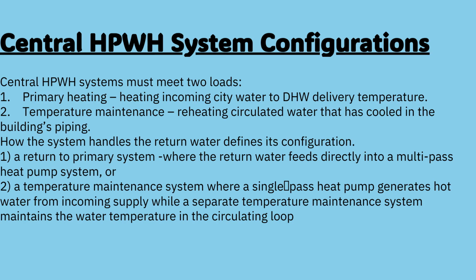Central heat pump water heating systems must serve two main loads: the primary heating load and the temperature maintenance load, or recirculation loop loss. The primary load is simple. It heats cold city water up to the domestic hot water temperature needed at faucets and showers. The temperature maintenance load is more subtle. As hot water circulates through the building, it loses heat in the piping. That returning water needs reheating to make sure occupants don't get lukewarm water. How we handle that returning water defines the system configuration.